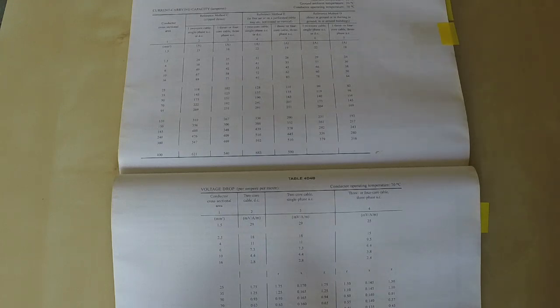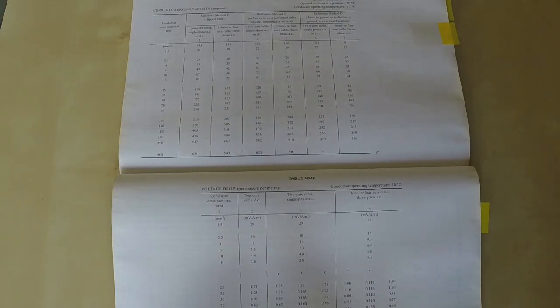If you find that after working out your volt drop it's above the maximum allowed—which is 6% or 8% of the voltage you're working with—then you simply do the same calculation again using a larger cable. The larger the cable, the less the volt drop.